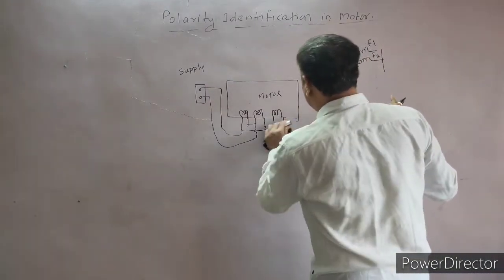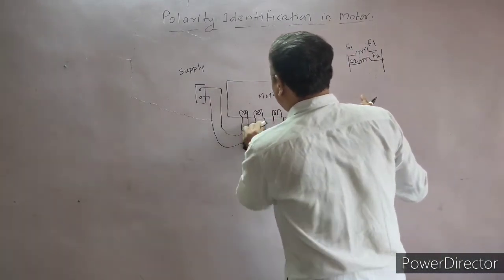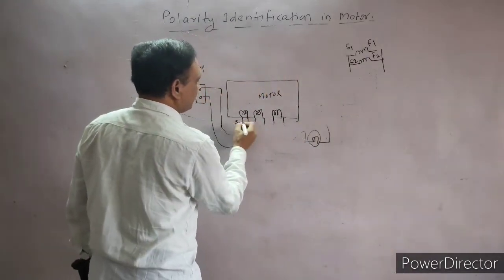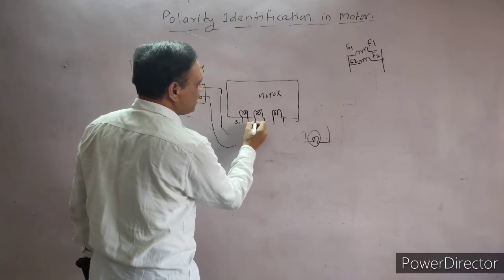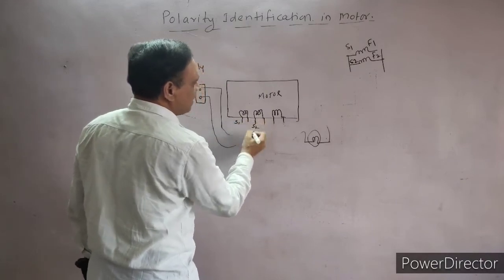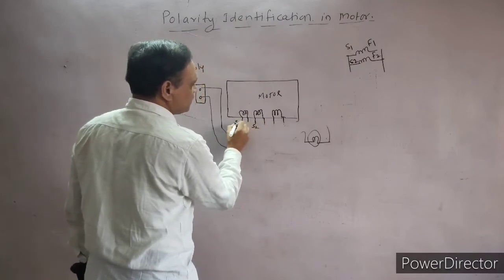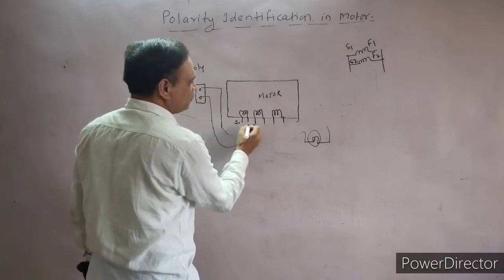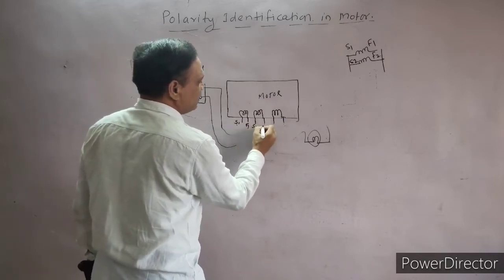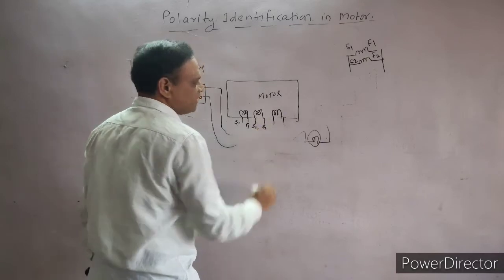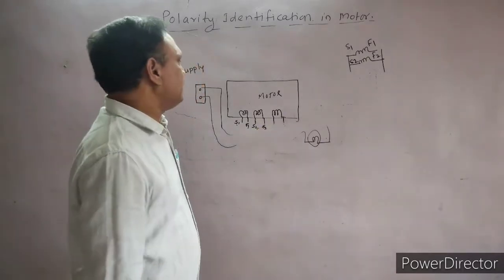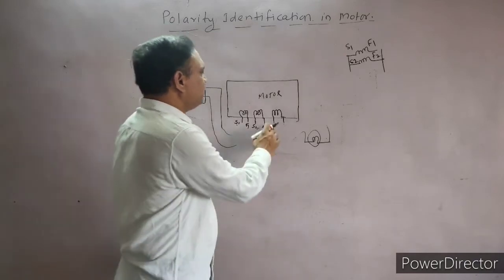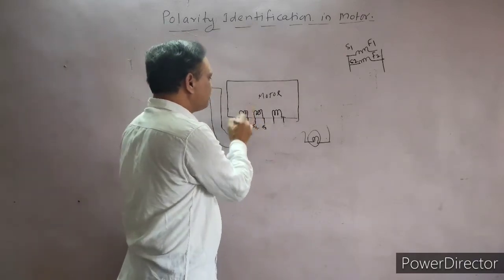So if the lamp glows, we can clearly say this is S1 — starting end one — and since the lamp glowed when these two terminals were connected together, these are both starting ends. Therefore, this is S1, this is S2, and the remaining terminals are the finishing ends — F1 and F2 of the respective coils. Now the same procedure will be repeated for the remaining two terminals.